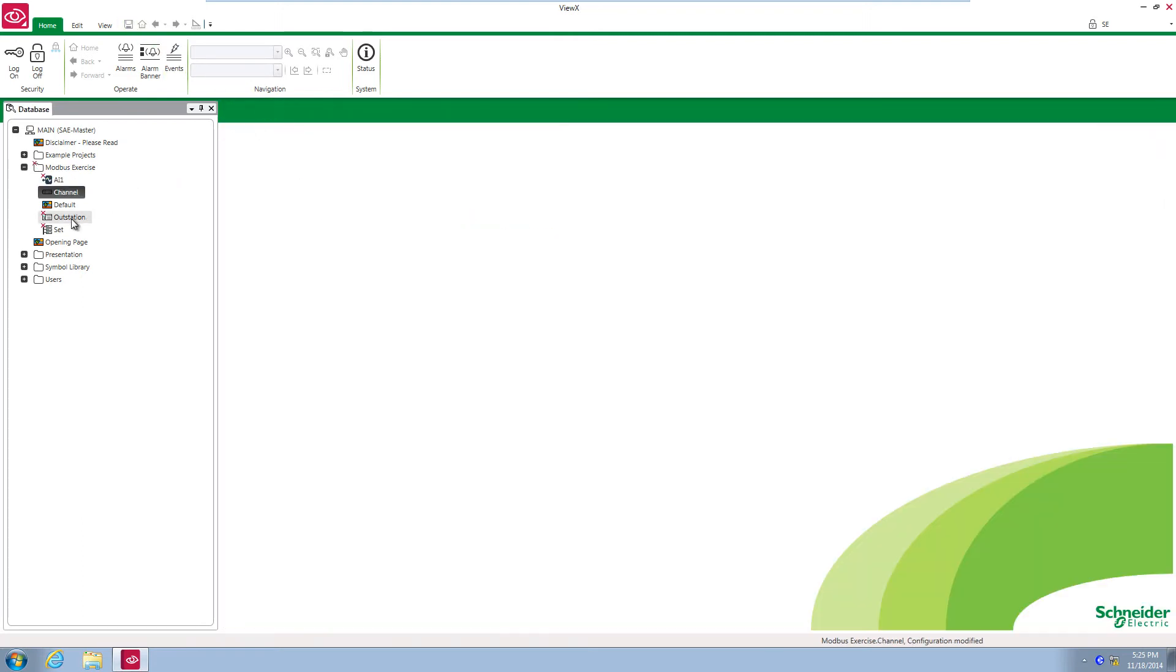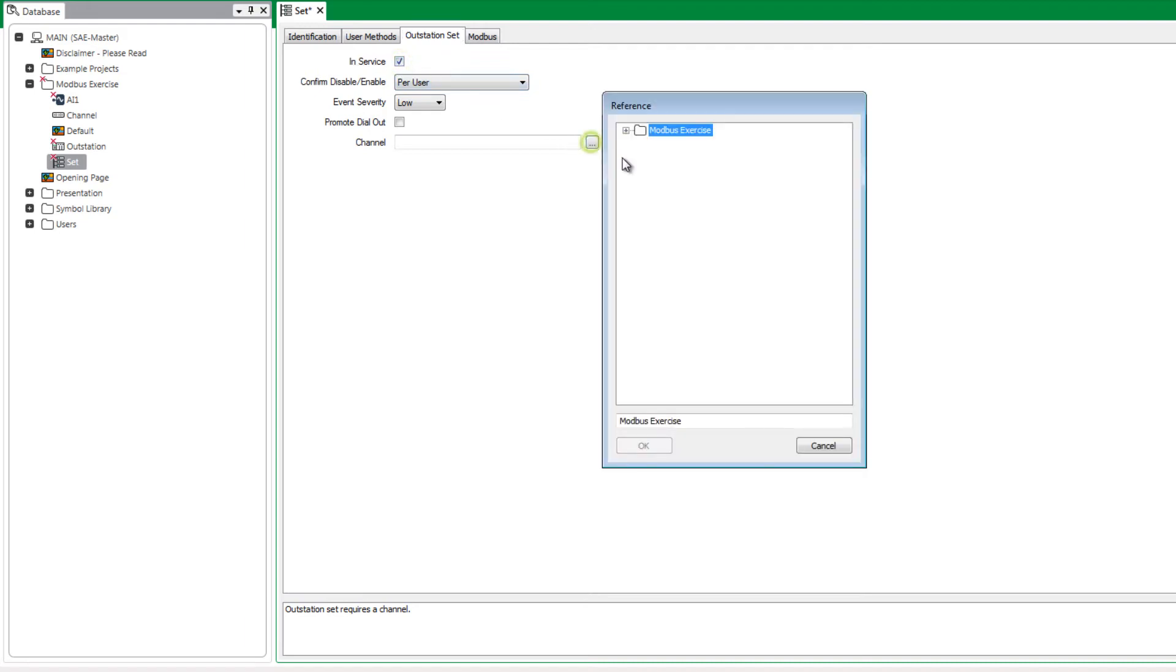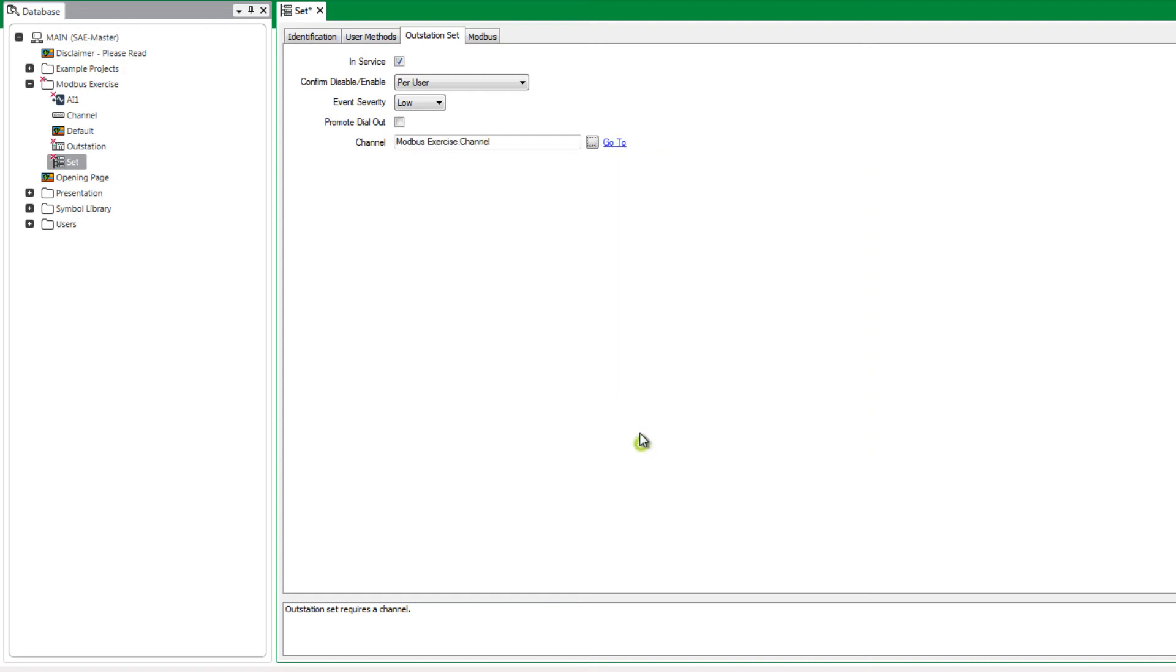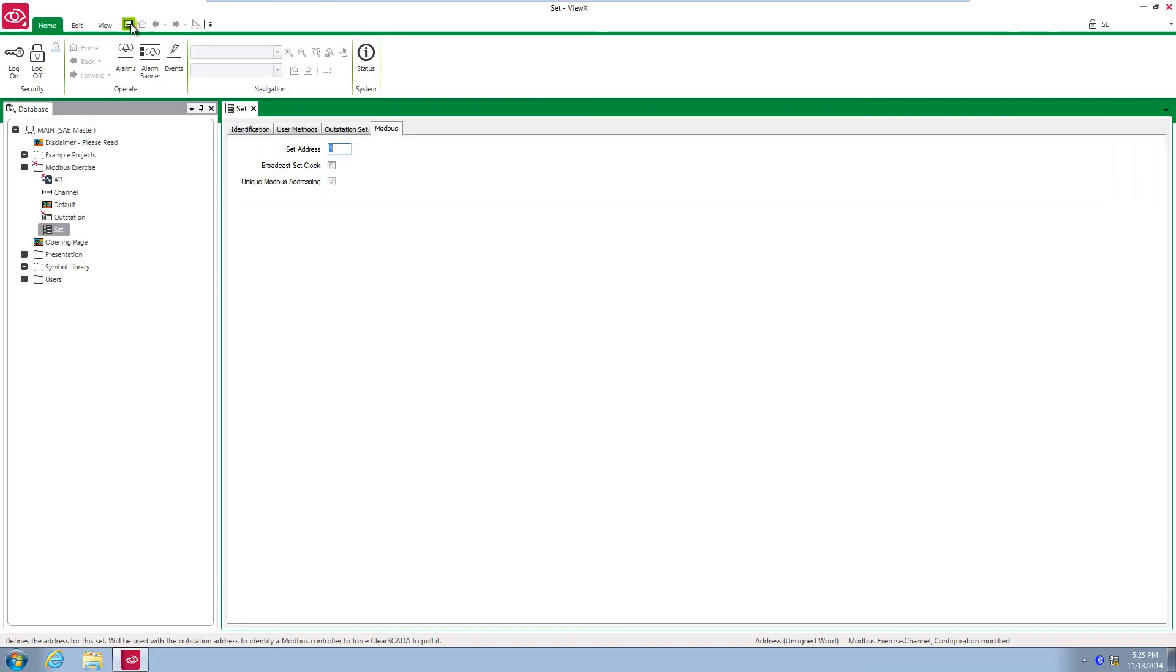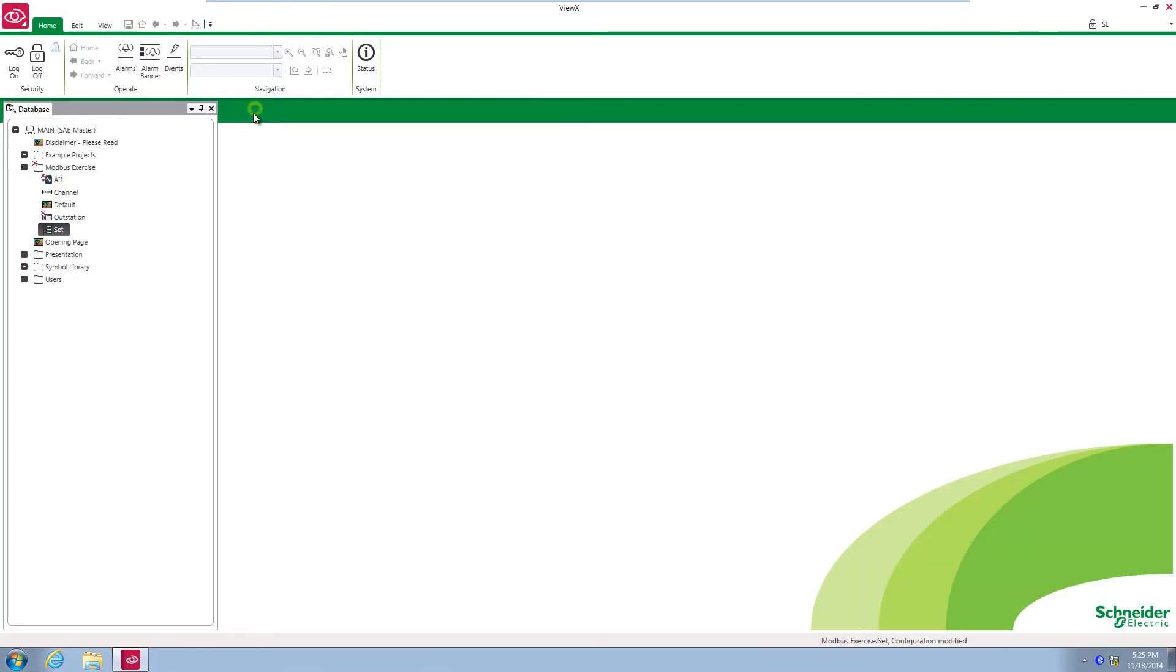The outstation set ties groups of outstations together. In Modbus for example, outstations connected to one set have a common Modbus master address. On the set object, go to the outstation set tab and put it in service. Below you'll see the channel field. Click browse and navigate to the channel object. Open the Modbus tab and set the address to 1. Save and close the object configuration form.